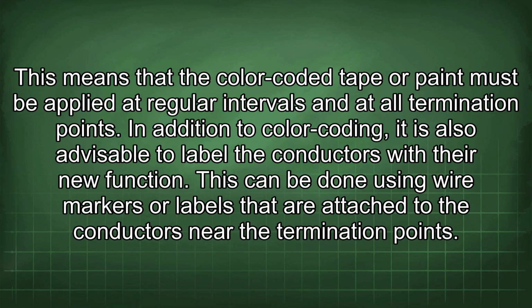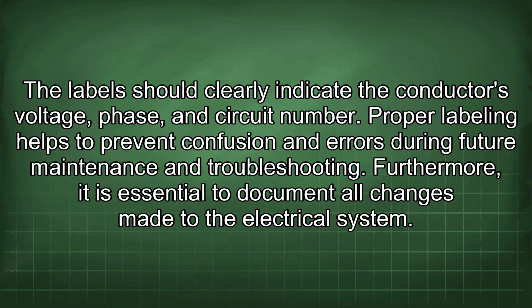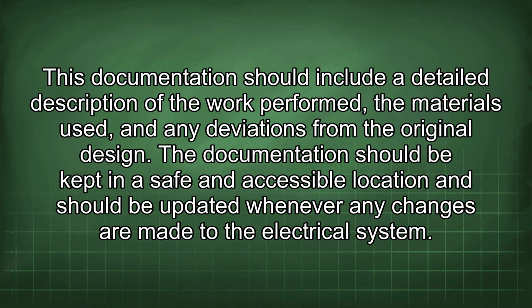In addition to color coding, it is also advisable to label the conductors with a new function. This can be done using wire markers or labels that are attached to the conductors near the termination points. The label should clearly indicate the conductor's voltage, phase, and circuit number. Proper labeling helps to prevent confusion and errors during future maintenance and troubleshooting. Furthermore, it is essential to document all changes made to the electrical system. This documentation should include a detailed description of the work performed, the materials used, and any deviations from the original design. The documentation should be kept in a safe and accessible location and should be updated whenever any changes are made to the electrical system.